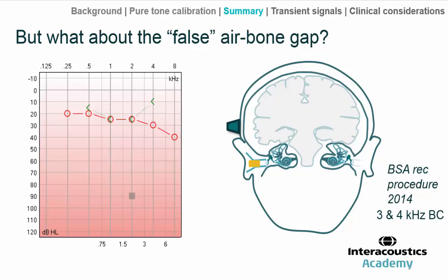The apparent air-bone gap remains. It isn't that there isn't any airborne radiation — that's not really what we think is the problem. Rather, if the reference equivalent threshold force levels were calculated on a group of normally hearing young adults who themselves had their ears plugged at 3 and 4 kHz when measuring bone conduction, then the effect of any airborne radiation should be cancelled out. So that's potentially the most likely reason why we don't see any effect of plugging.